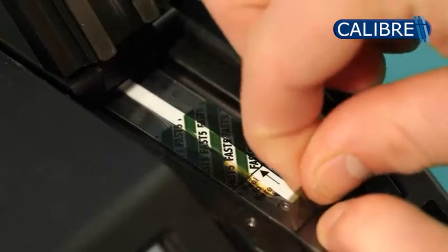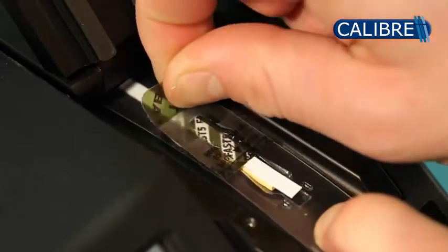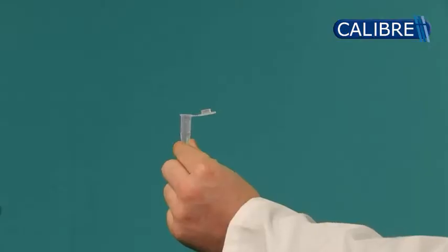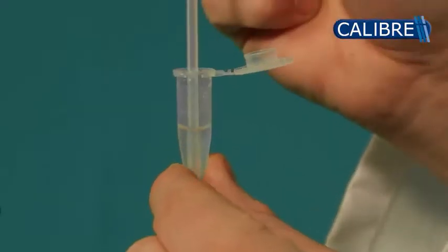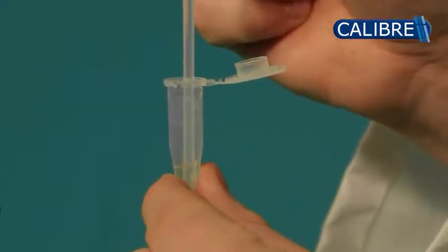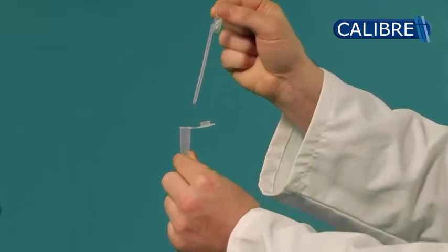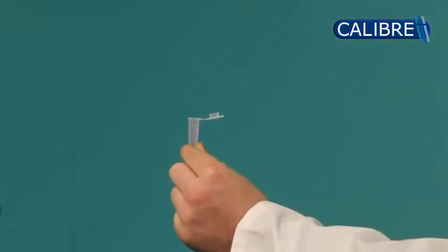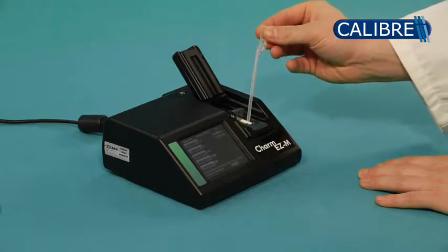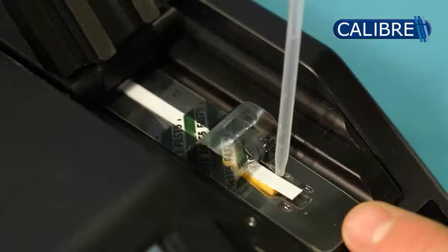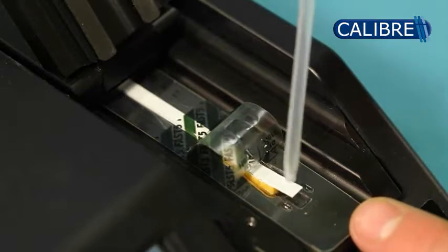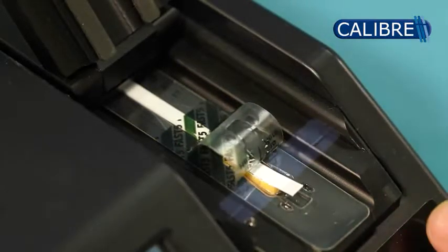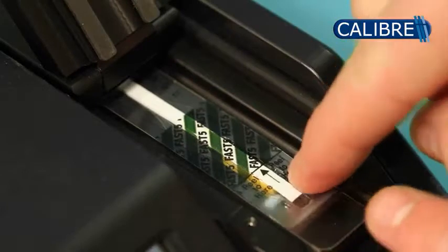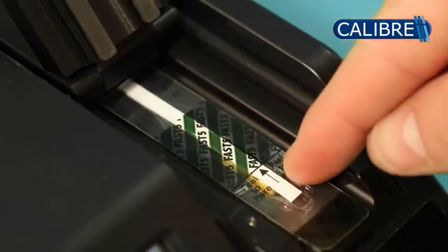Now, peel the tape back to the Peel to Here line. Using the 300 microliter pipette, draw up the sample by firmly squeezing the top chamber on the pipette and avoid drawing up bubbles. Then, holding the pipette vertically, slowly pipette 300 microliters of sample into the sample compartment on the test strip, which is clearly marked by horizontal lines on the reader on either side of the strip. Now reseal the tape over the sample compartment and close the lid.